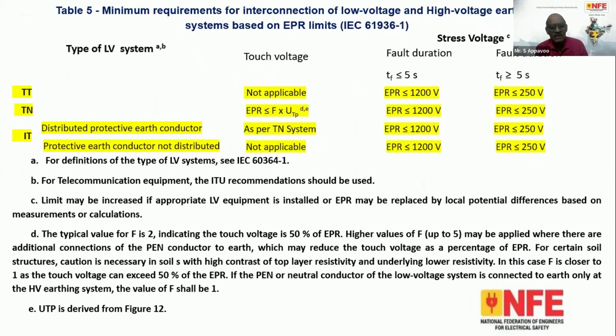The temporary overvoltage is a major concern. Unlike transients due to surges or lightning, there are provisions to contain these transients by use of a lightning protection system or lightning arresters or surge protectors that can operate in microseconds. But our temporary overvoltage is just like mimicking the supply frequency voltage. It is undamped. Temporary overvoltage is not yet fully defined. It is undamped supply frequency which occurs during load rejection or any fault. So this undamped is nothing but similar to the supply frequency voltage, undamped, and the voltage will be higher.